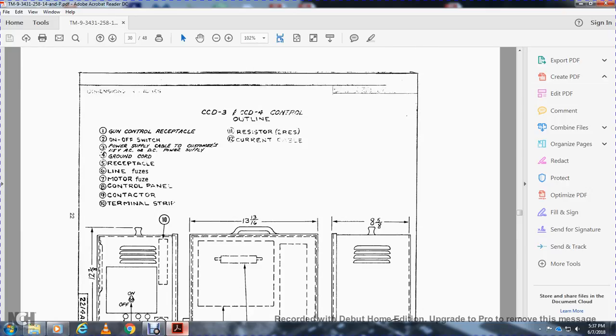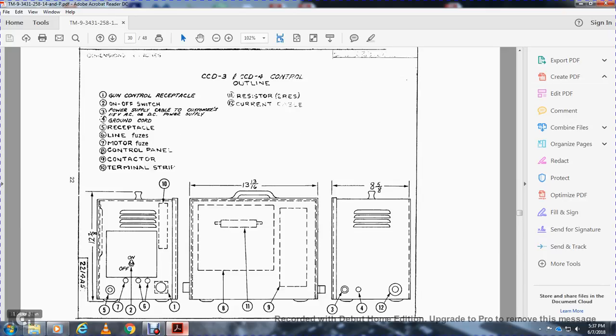Alright, this is your CCD3 or CCD4 control outline. One is your gun control receptacle. 2 would be your on-off switch. 3 is the power supply, with the customer's 115 volt AC or DC power supply. 4 would be your ground cord. 5 is your receptacle. 6 is the line fuses. 7 is your motor fuse. 8 is your control panel. 9 is your contactor.